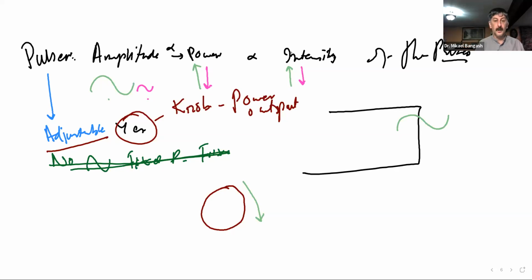Or yes, if we decrease the power output, mainly by turning that knob anti-clockwise, that will decrease the intensity of the sound wave. Now please keep in mind, the sound wave that is being transmitted. Or we can say the intensity of the pulse, or the power of the pulse, or the amplitude of the pulse will be lower. Which mainly means lesser sound energy will be transmitted by the transducer.